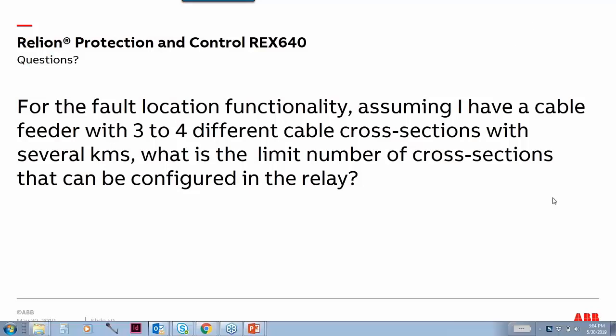So the first question that we have is for the fault location functionality, assuming I have a cable feeder with 3 to 4 different cable cross-sections with several kilometers, what is the limit number of cross-sections that can be configured in the relay? Yeah, in this case, the fault locator has to be applied for homogeneous cable. If you have different cross-sections throughout the feeder, this specific element would not be suitable for this application.